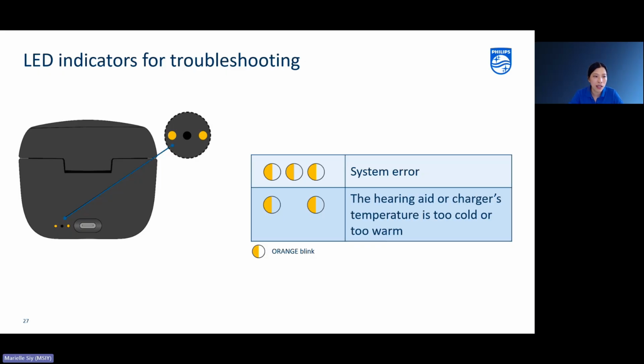The second pattern is two LEDs blinking orange. This means that the hearing aids or the charger's temperature is too cold or too warm for it to start charging. What you can do or tell your client is to move the Charger Plus with the hearing aids to a location between 5 to 40 degrees centigrade, not too hot, not too cold. The charging will automatically start again once the temperature is within the safe range. And of course, the last thing you see here, if you only see one orange blink, that simply means that the power bank is charging. So this is not an error.